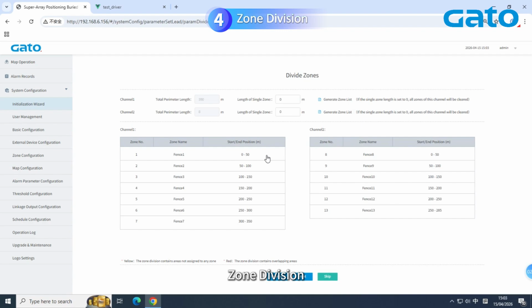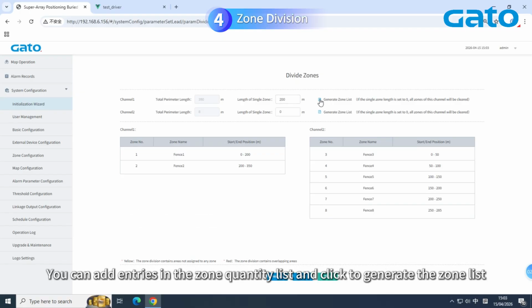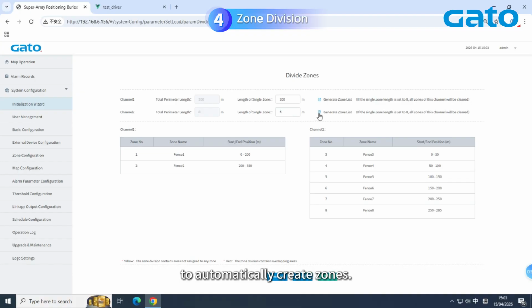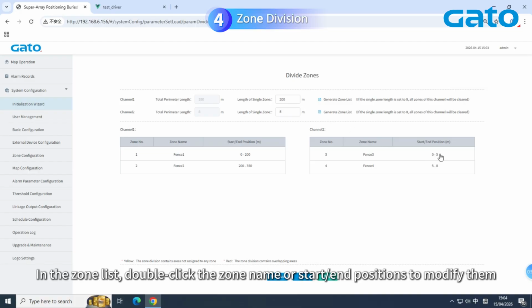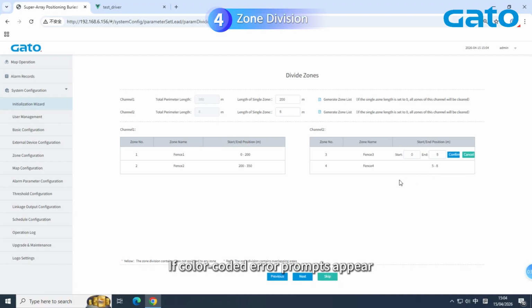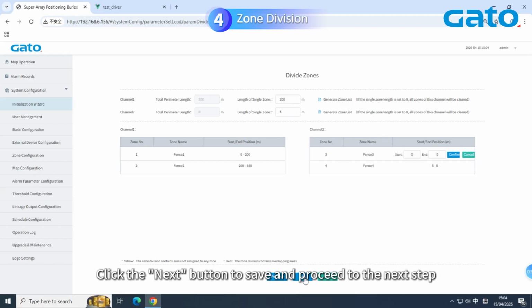Zone division. For example, to evenly distribute zone lengths, you can add entries in the zone quantity list and click to generate the zone list to automatically create zones. In the zone list, double-click the zone name or start or end positions to modify them. If color-coded error prompts appear, click the Next button to save and proceed to the next step. Click the Skip button if this step is not required.